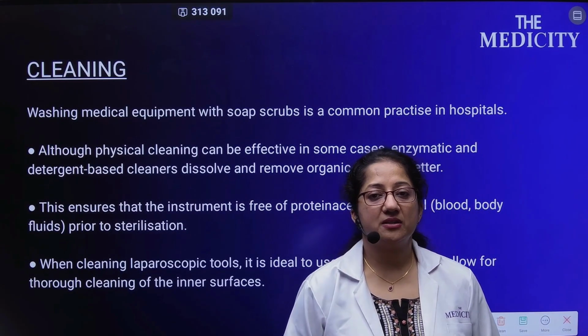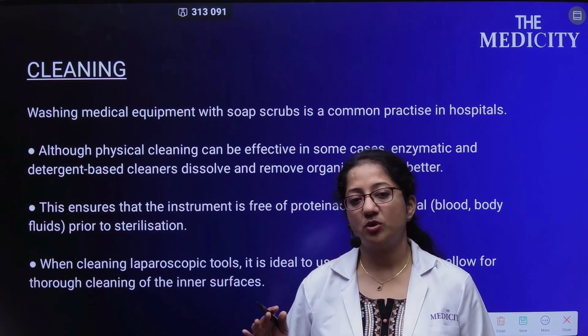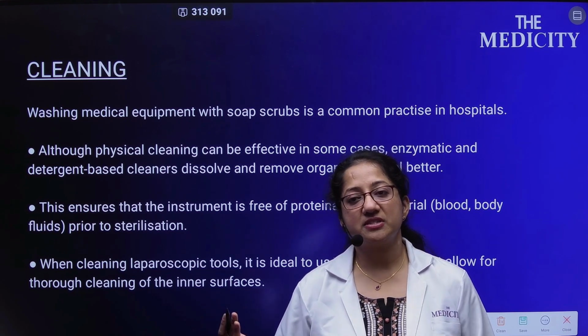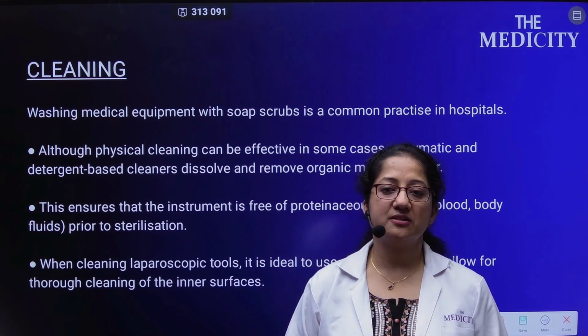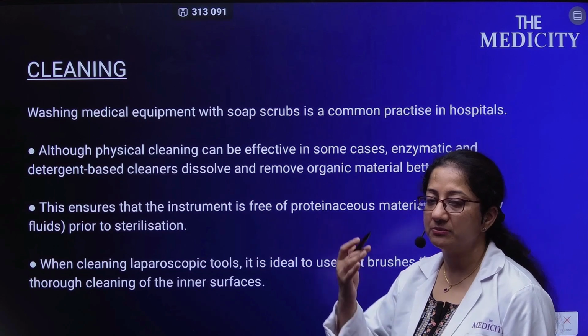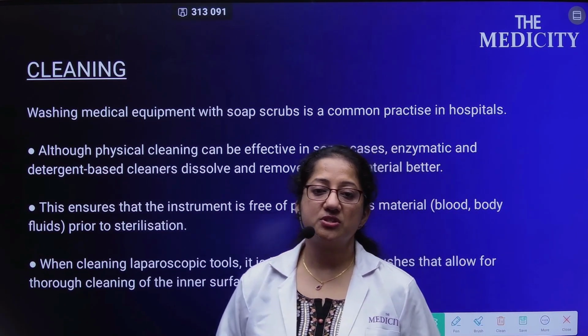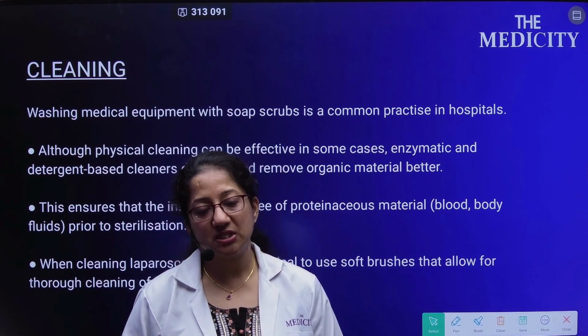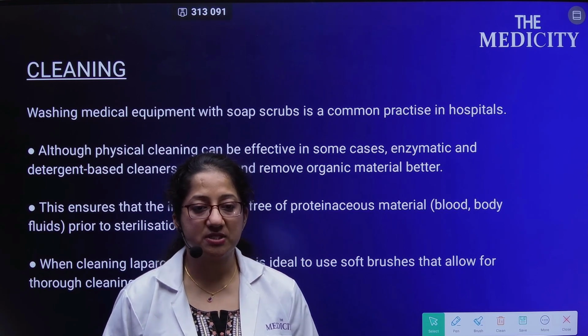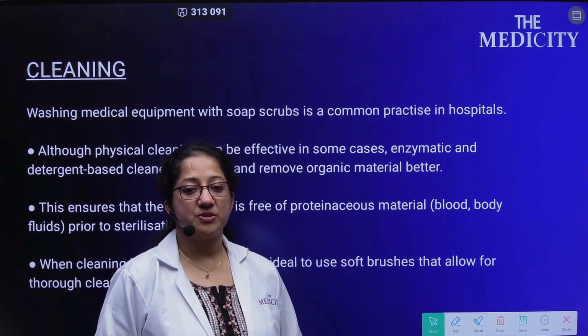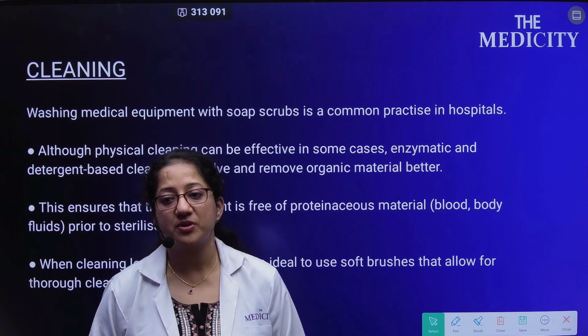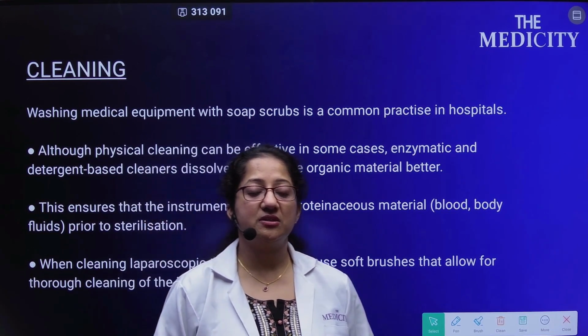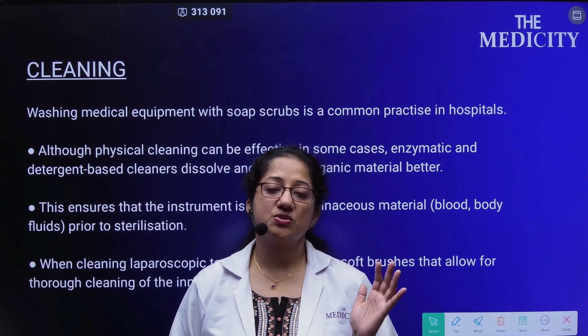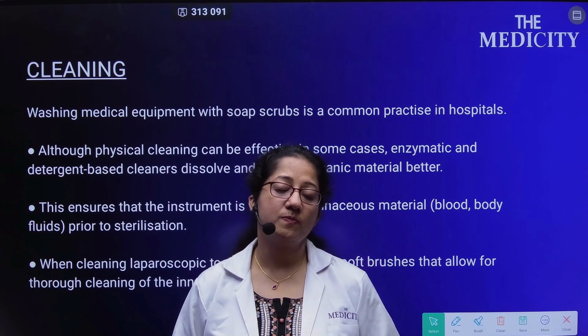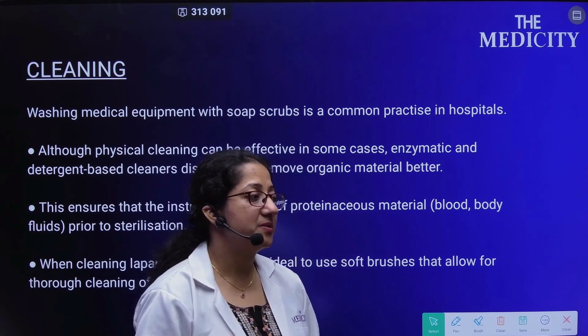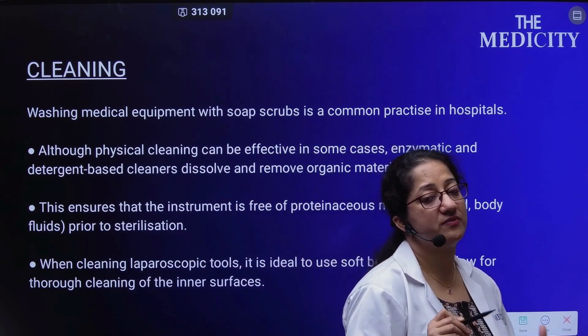Washing the medical equipment with soap scrubs is common. Although physical cleaning can be effective in some cases, enzymatic and detergent-based cleaners dissolve and remove the material better. This ensures the instrument is free of proteinaceous material like blood and body fluids. When cleaning the laparoscopic instruments, it is ideal to use soft brushes which allow thorough cleaning of the inner surfaces, especially when there are serrations in the edges. Those serrations can harbor bacteria, blood and body fluid, which need to be cleaned.